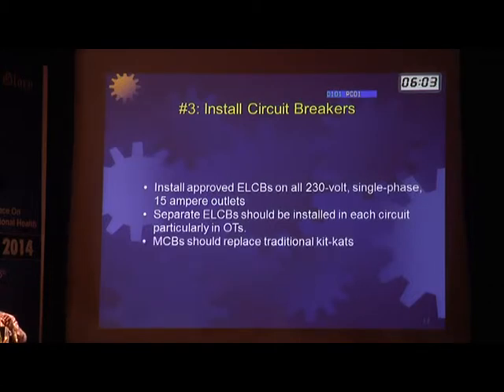MCBs should replace traditional kit cats. The main reason for fire in many places is that these fuse kit cats are connected with very thick wires - the electrician sees that a small wire burns up, so he puts a very thick wire instead. I've seen this in strips. I've been visiting mission hospitals across the country, at least some 50 of them, and practically everywhere I find electrical dangers. The fuse kit cat is missing, and there's a strip put across the fuse. That can lead to a major disaster. The moment the fuse blows, it means there's something wrong down the line.